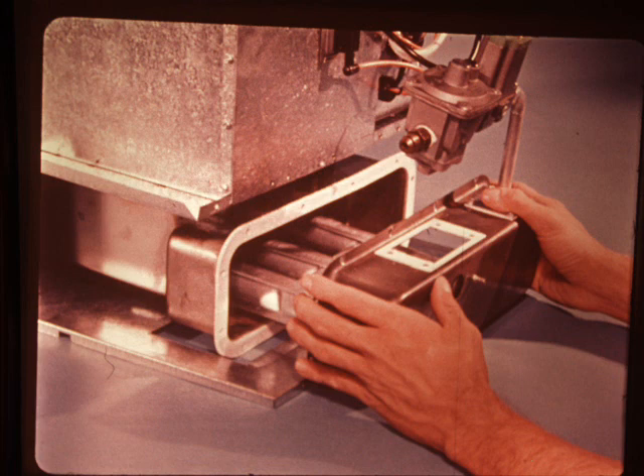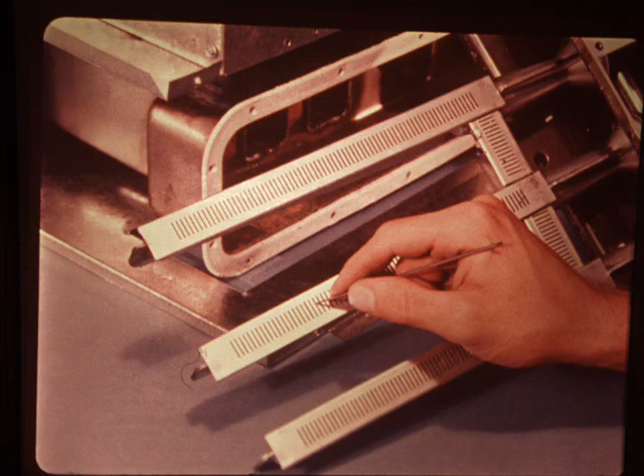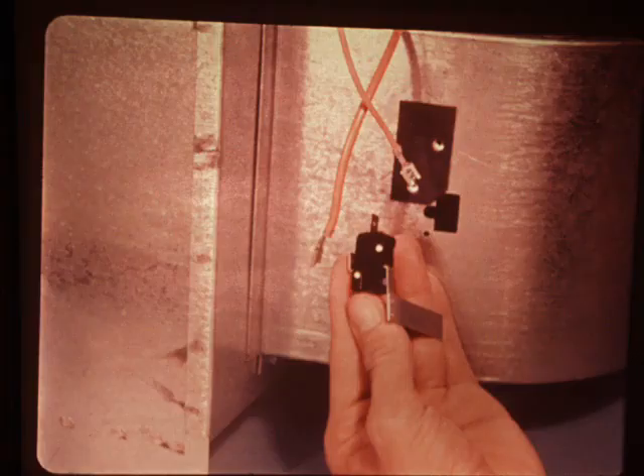Check the combustion chamber for accumulated soot if you're removing the burners. If there's a lot of soot, you'll want to check for excessively high LP gas pressure. This is usually the cause, since there's no air adjustment on this furnace. Whenever the burners are removed, check the orifices for obstructions. They can be cleaned with a wooden toothpick.